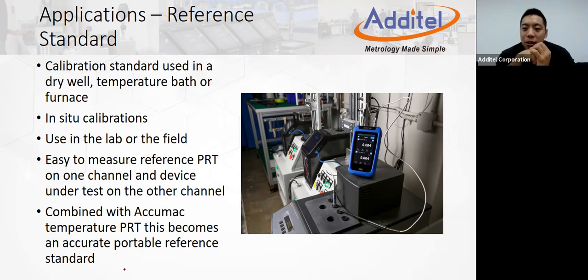The other, or what we call the regular on-site or on-field calibration, what you need to do is you need to remove or disassemble the DUT from the line, and then put the DUT and also your standard in the external heating source, like a bath or dry well, and then make the calibration. And then after that, you need to put back your DUT into the line. So there are two different ways to do it. 282 supports both of them. So you don't have to remove the DUT if this is pretty big or pretty hard to disassemble.